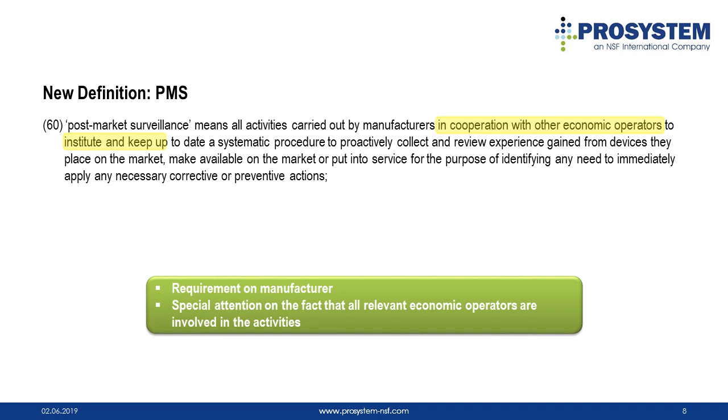PMS is defined to be all activities carried out by manufacturer in cooperation with other economic operators to institute and keep up to date a systematic procedure to proactively collect and review experience gained from devices they place on the market, make available on the market, or put into service for the purpose of identifying any need to immediately apply any necessary corrective and preventive actions.